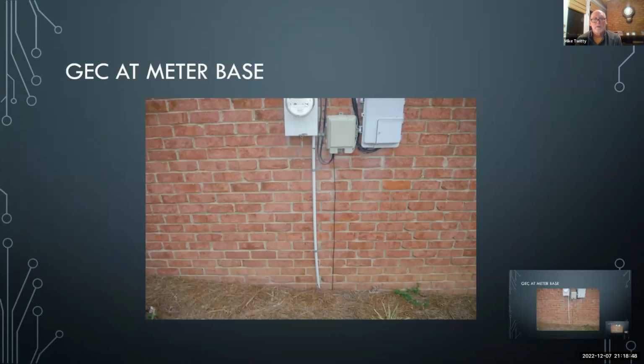Here's one. I keep saying equipment, I apologize, this is the grounding electrode conductor going to the ground rod right here from the meter base. This is a back-to-back. Right on the inside wall of this basement is a service panel. In some jurisdictions, it could have gone in there, but our utility said it's got to go here. They won't give you a service release if it does not land in there.